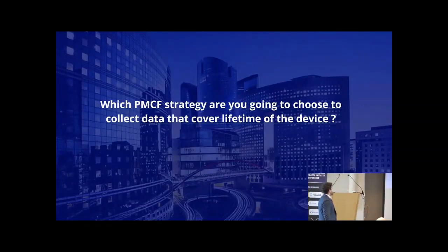What PMCF strategy are you going to choose to collect the data that cover the lifetime? I just come back to the story of the implantable device and the patch, because they are two implants that are done for the lifetime of the device. So we've done the retrospective study in 6 months, and it was successful. We retrieved data for 3 years, but it is not enough for the notified body. You need to go further. You need to collect after.